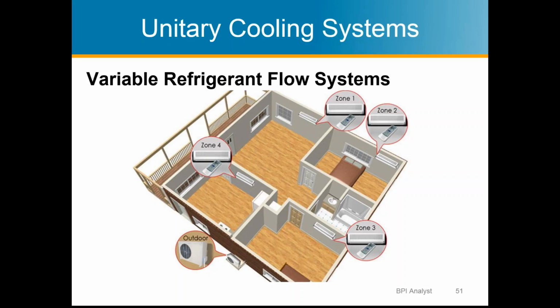And then, of course, if you're not in the room, certain rooms can just be shut off. With constant volume ACs, the standard package or split systems, it's really not good to close a register and shut the door for those systems, because again, it increases the static pressure in the system, which is bad for the system. So you shouldn't ever close a vent in a constant volume system. It actually decreases efficiency more than just leaving it on, cooling a room even if you're not in it. So that's the advantage of variable refrigerant flow systems.